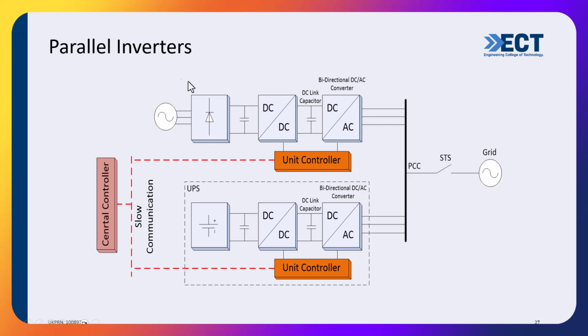We have two generators. These two generators generate DC regardless of what they are, and we convert that DC to another step-up DC voltage, and then convert it from DC to AC. So we have one unit here and another unit here. That unit is called unidirectional because it can push power to the bus but can't consume it. The same thing here, but this one is bidirectional, meaning it can absorb power to charge the battery, or push power out. And we have this switch that can control whether we are on-grid or off-grid.